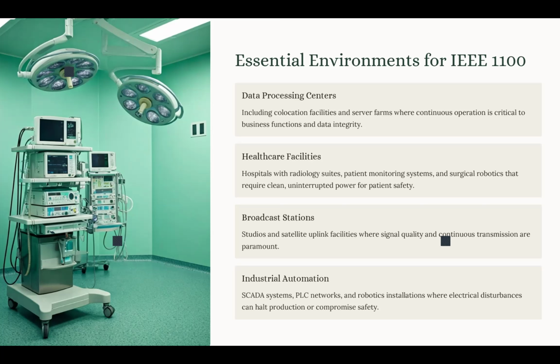Now, another very vulnerable environment is healthcare facilities. We know that medical equipment like MRI, CT scan, or surgical robots, even a momentary power disturbance can cause errors in diagnostics or even a surgical interruption. You can imagine how severe the consequences of those issues could be. So we need to make sure we follow IEEE 1100 to address those vulnerabilities. There are several practices recommended by IEEE 1100 for healthcare systems. One is functional grounding for medical electronics, or strict voltage and transient control.